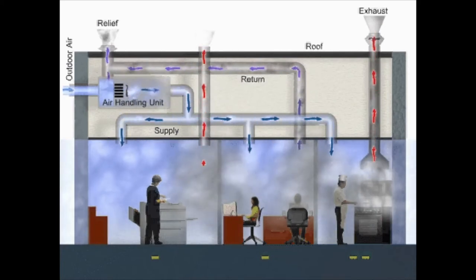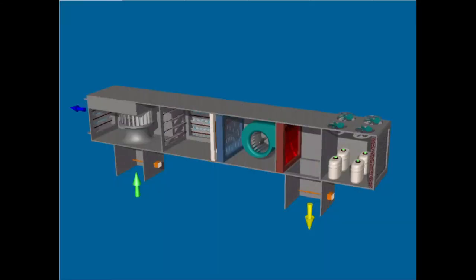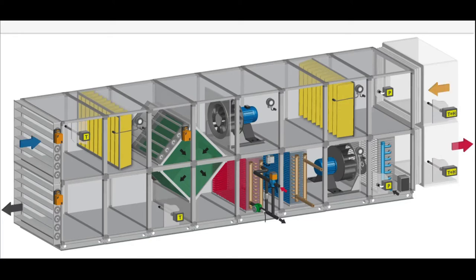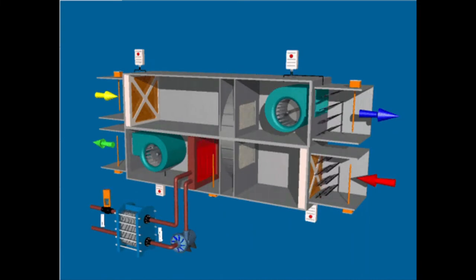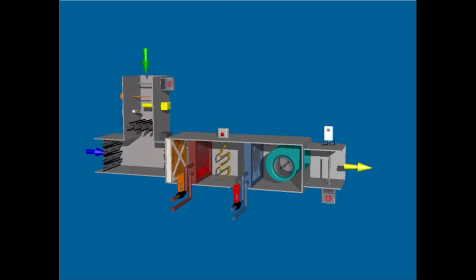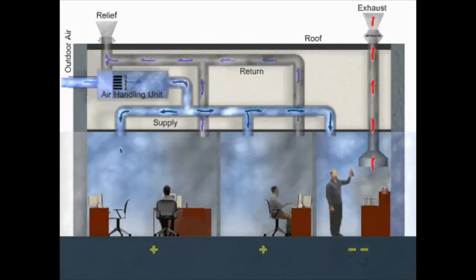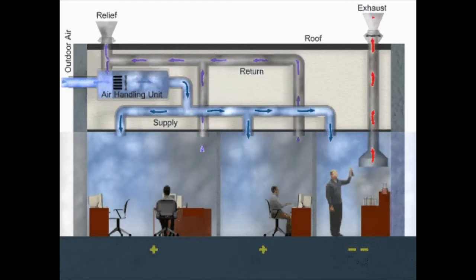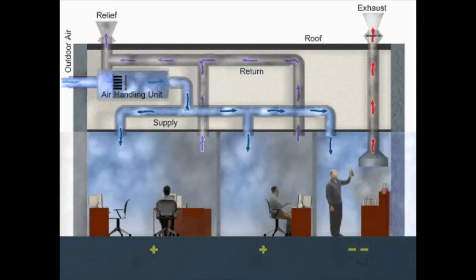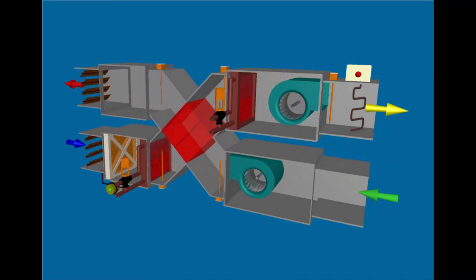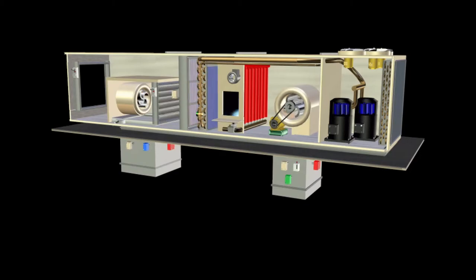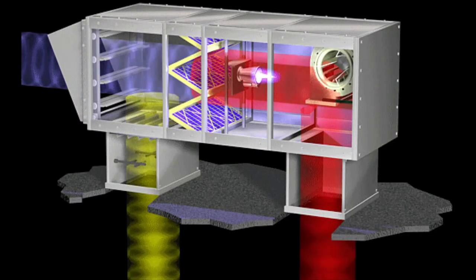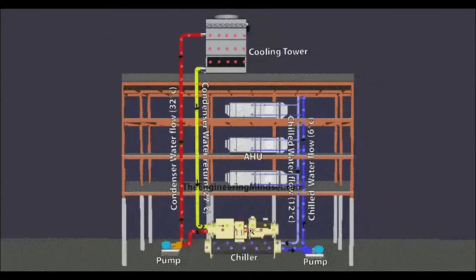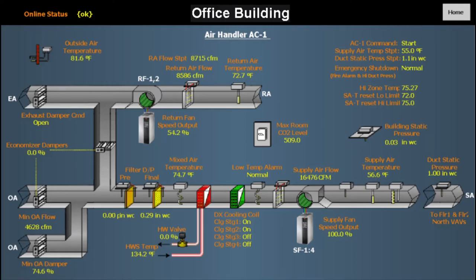And then on top of that, it could also be that you have natural ventilation in the building. But you have other heating and air conditioning systems that are local to each room or each zone within a building. Yeah, we see a lot of just natural ventilation, which is operable windows, and then some sort of radiation, some hot water radiation underneath it. Common in our area too. And then you can also have variable refrigerant volume systems, also known as what, Joe? Well, you have VRF and then VRV, so either volume or flow. They're essentially the same, just different manufacturers call them different things. Proprietary. Those are refrigerant-based air conditioning systems, and they usually do not have a ventilation part to them. I know a lot of older hospitals will have dual duct systems where they have one duct system that's hot air, one that's cold air. And then they mix it locally.